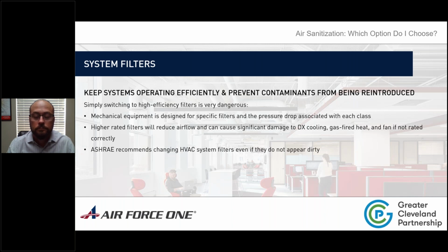It lowers your airflow. It can cause you heat exchanger problems during the summer or wintertime, and then cooling problems, specifically either short cycling or not enough airflow and freeze ups on your evaporator, which then reduces the life of your equipment. It's very important to make sure that you don't go beyond the capabilities of your equipment when it comes to filters.